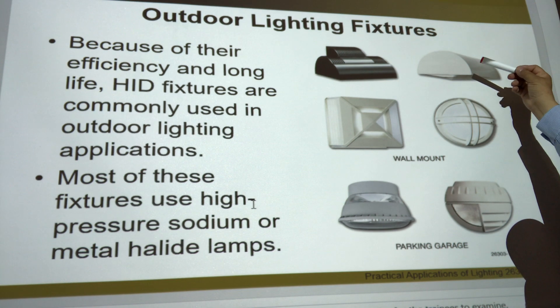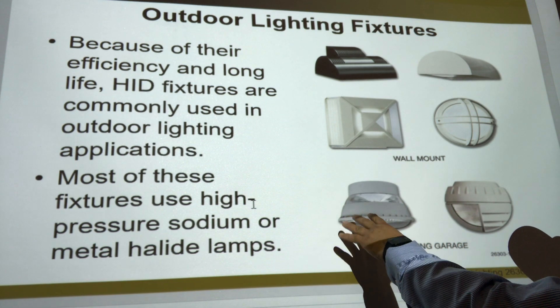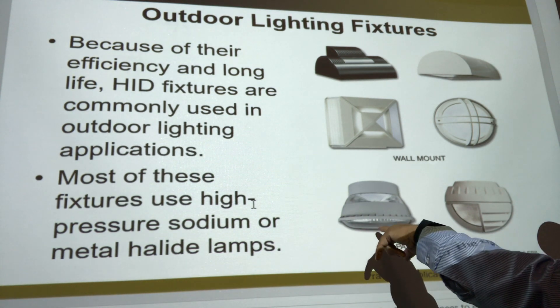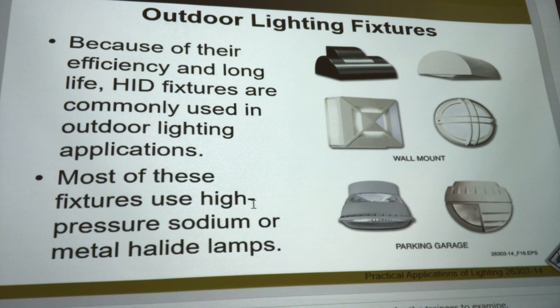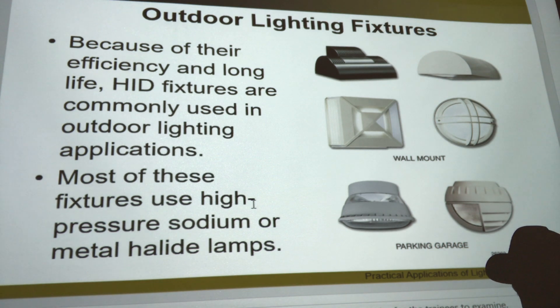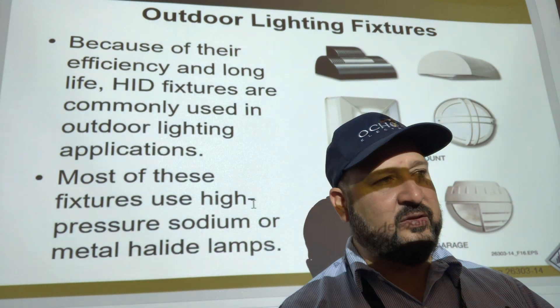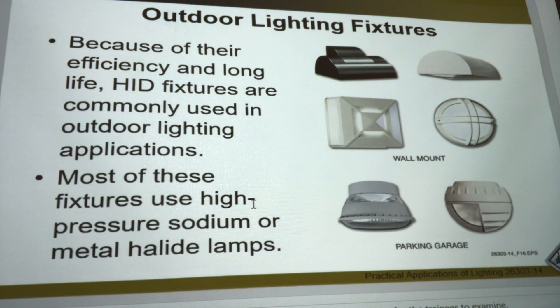For parking garages, you want a diffused light so it diffuses properly. In a parking structure, lights are spaced around 25 feet apart because you don't need that much light — the foot candle requirement for a parking structure is very different from a classroom. They just want you to be able to see, get in, get your car, and go. Also, how much daylight you have affects how many foot candles you need — that's the engineer's job, using a formula for daylight to determine nighttime foot candle requirements.